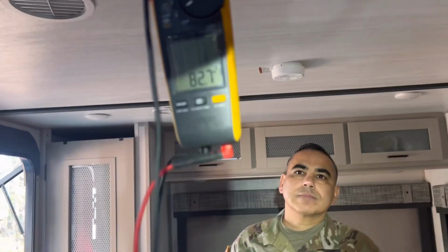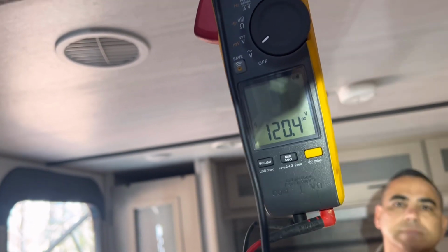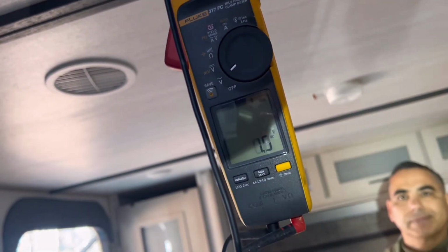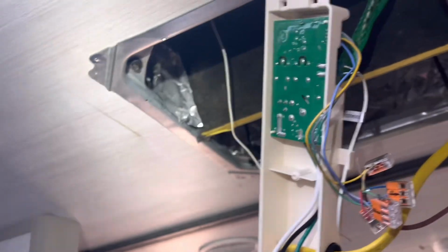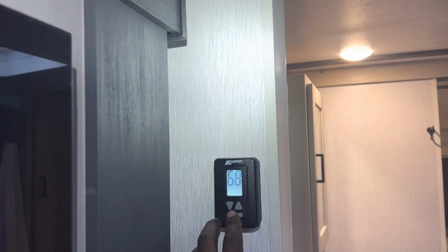Now go back to volts AC. All right, now we're on volts AC, and one side of this should be constant hot. All right, as you can see, I have 120 volts, but on the other side of the relay, nothing, 1.8 volts. So what that tells us is you have a bad relay, and those relays, as you can see, are soldered onto the board. So you have to replace the whole control board. So this is a definitive diagnosis that this control board is bad, specifically the compressor relay.